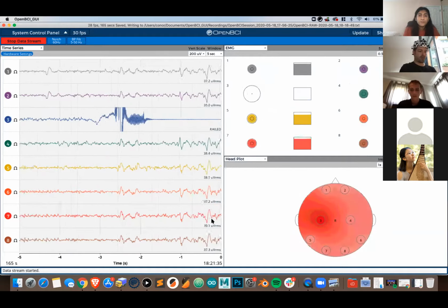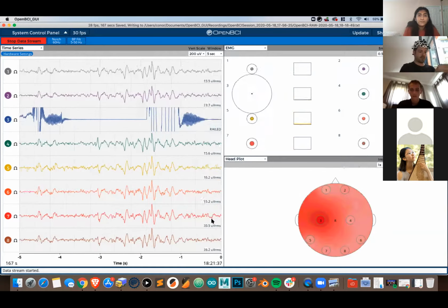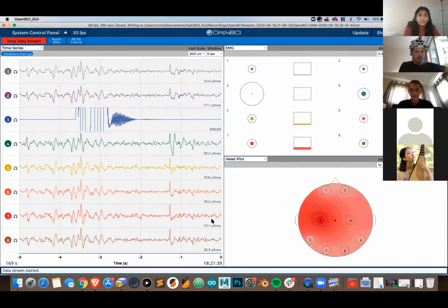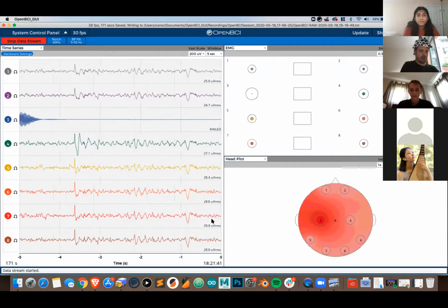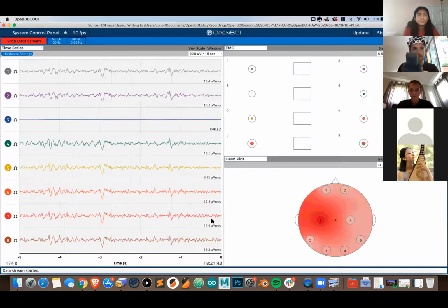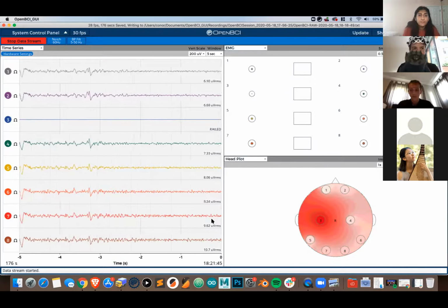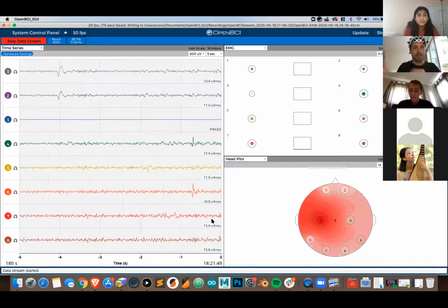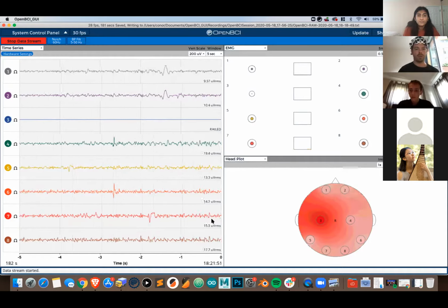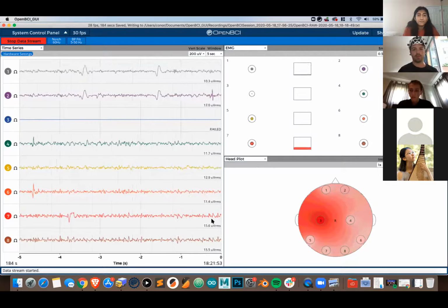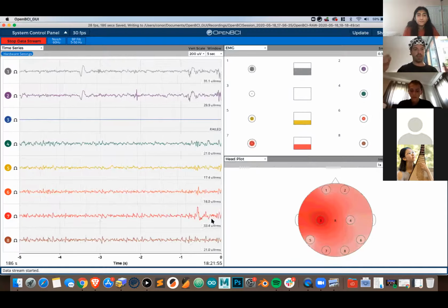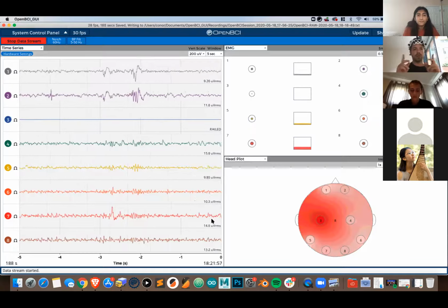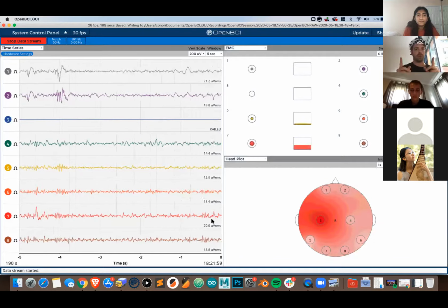Great question. So I brought a couple extras for the demo. The electrodes that are in the headset right now look like this. They're spiky, and they're metal. They're coated in silver chloride, which is a commonly used material for electrodes in dry EEG. The two most commonly used materials are gold and silver chloride.